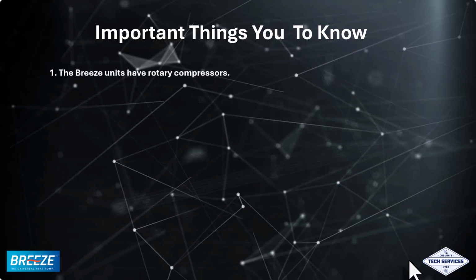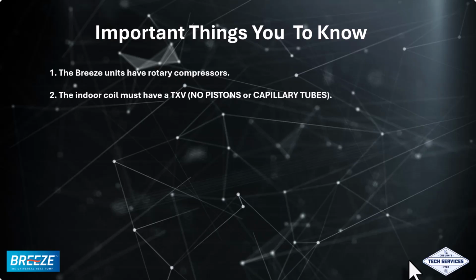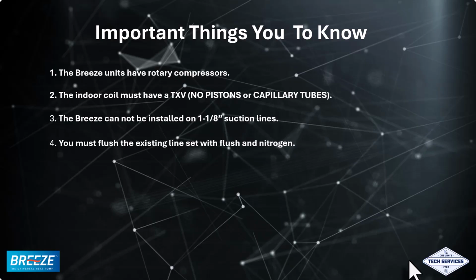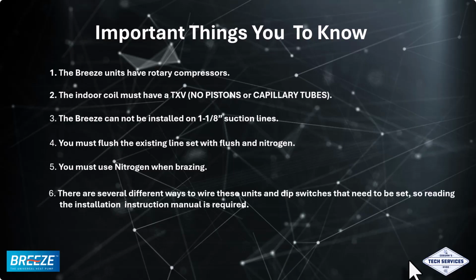Things you need to know: the Breeze units have rotary compressors. The indoor coil must have a TXV, no pistons or capillary tubes. The Breeze cannot be installed on an 1 1/8" suction line. You must flush the existing line sets with flush and nitrogen. You must use nitrogen when brazing.